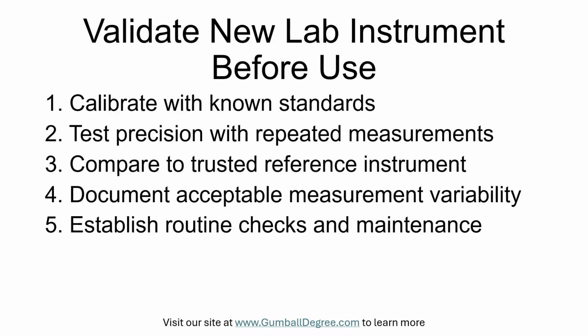You also compare those measurements to a trusted instrument or a certified sample to confirm accuracy, and you write down how much the new instrument can vary so you know what counts as acceptable. Finally, you set up routine checks and maintenance steps so the instrument keeps working the same way over time.